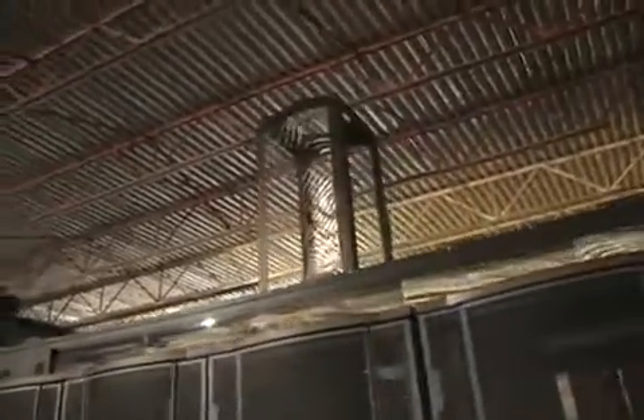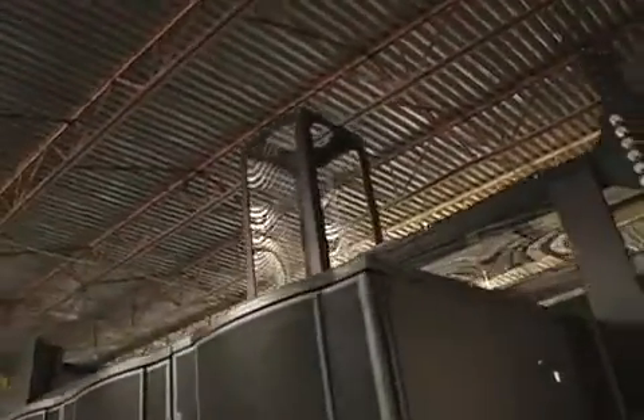Chimneys are provided. Right now on this unit there is physically just one chimney, but there are positions for five. You can actually go up to 10 chimneys if that's what you require for heat density and to maintain the proper CFM.